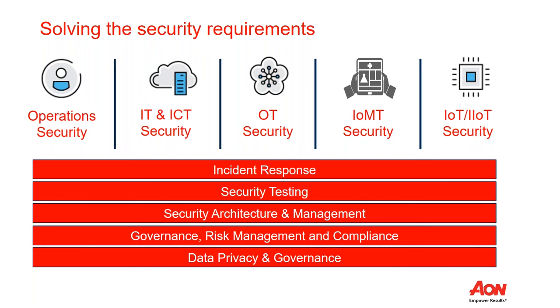If we refer to the cybersecurity guidance itself, section 3 is secure design and manufacture. One of the most critical images in the whole document is the risk management process, found on page 17, Figure 6, entitled 'Information Flow in Safety and Security Risk Management for Medical Devices.' This sets out a risk management process that should be part of the entire life cycle of the device, essentially to ensure a secure product life cycle.